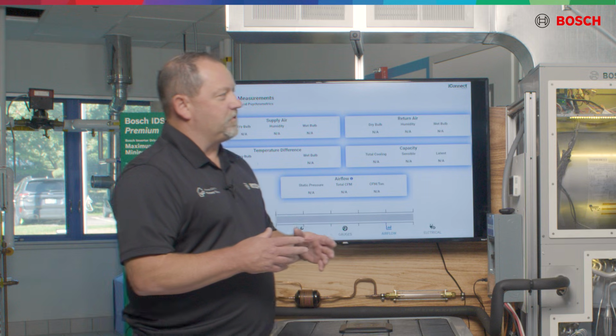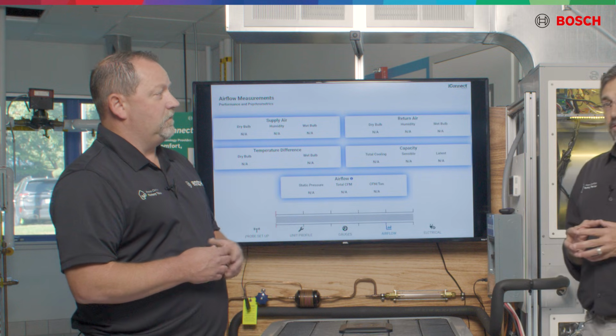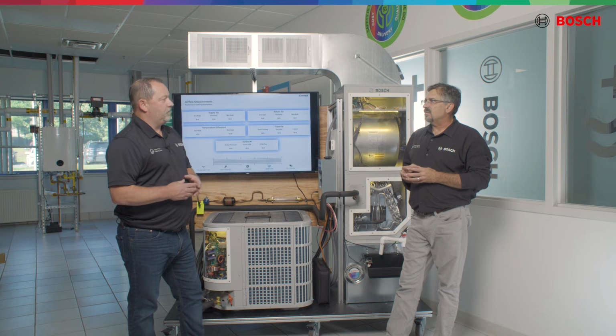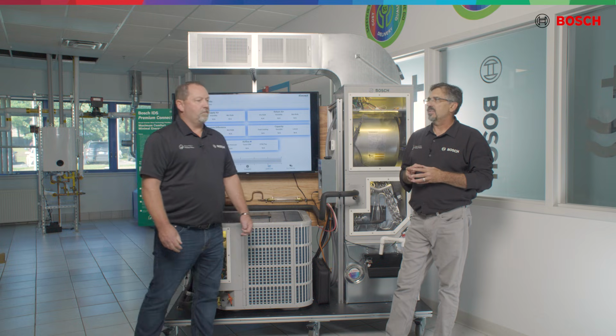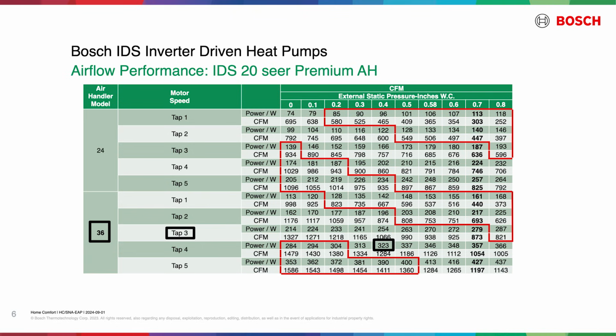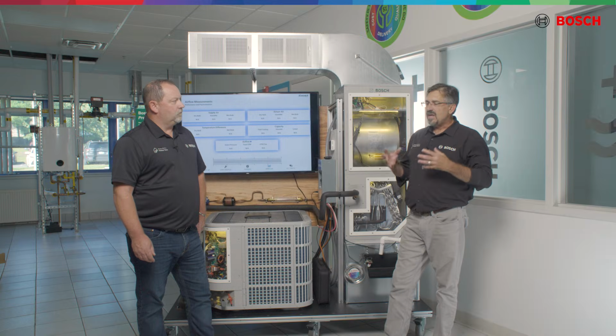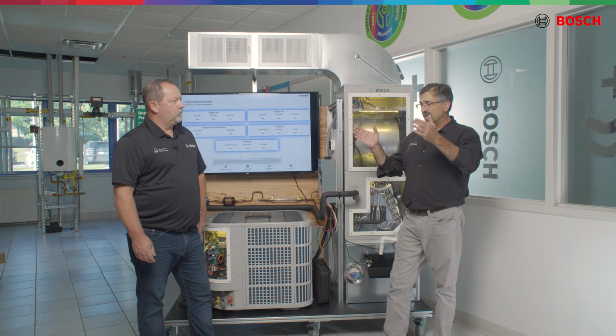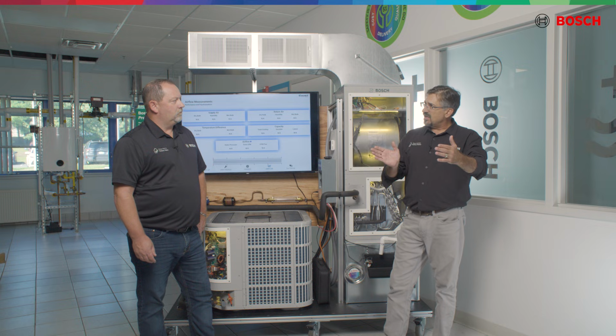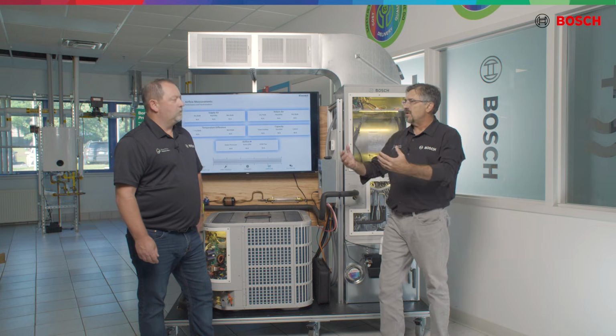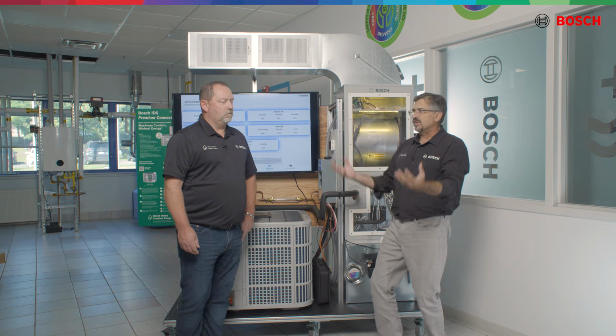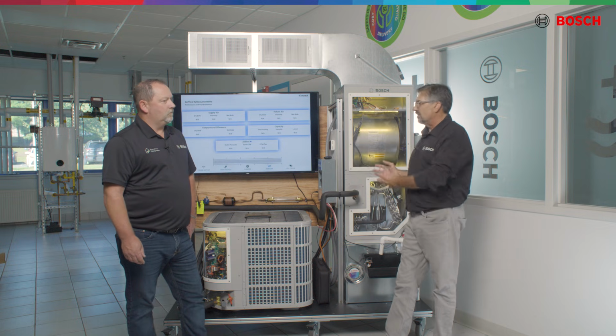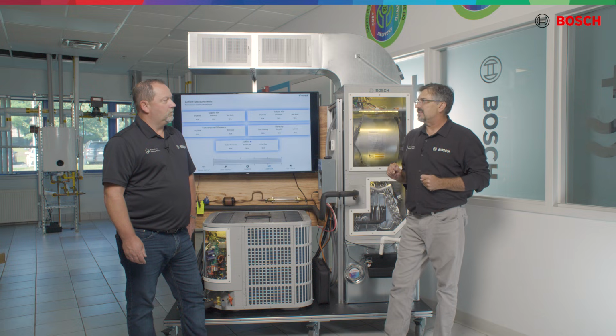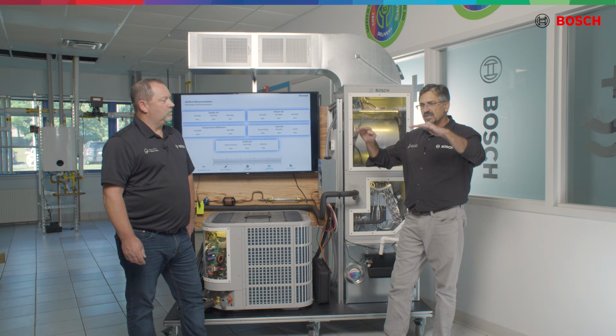So there might be some airflow setting adjustments that we might need to make as well. Is that what you're saying? That's correct. No matter when we install an inverter system, we have got to shoot for 350 CFM per ton. If we do not achieve that, the system will not work correctly. One of the most common problems is overcharging a system with too much refrigerant. The reason is that when we have high static pressure from insufficient ductwork, large media filter cabinets, the airflow is reduced. When that airflow is reduced, our CFMs are reduced. We're not delivering the amount of air we need over this coil. That Bosch system recognizes it. My suction pressure drops, the system backs down.